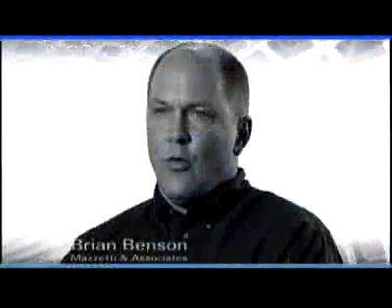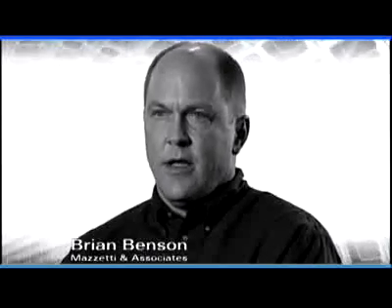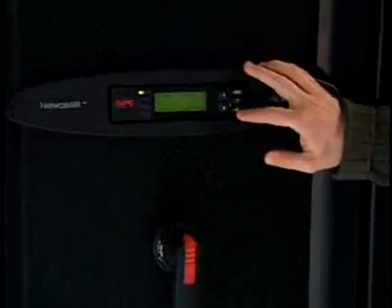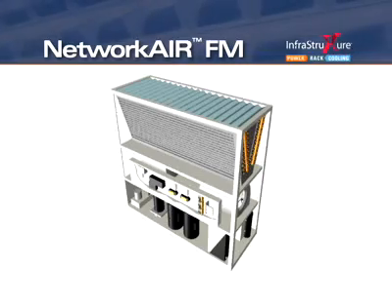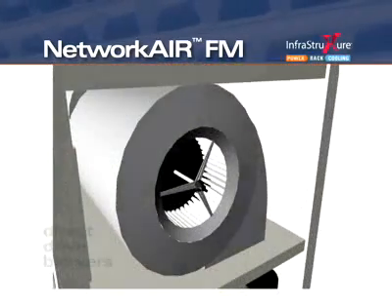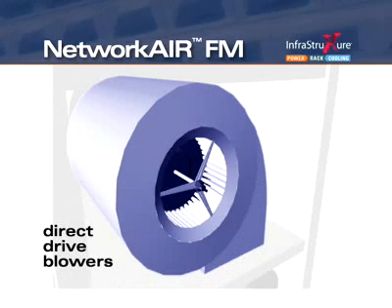The biggest weakness in traditional data floor cooling equipment is belt-driven fans, constant speed belt-driven fans. One of the big advantages to not only direct drive technology, but also variable speed direct drive technology is that you can change how much air is delivered to the floor. Designed with integral direct drive blower and motor assemblies, the Network Air FM eliminates the need for belts, pulleys, long drive shafts, and separate motors that are common single points of failure in other systems.